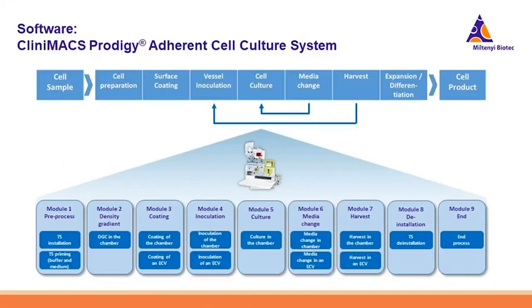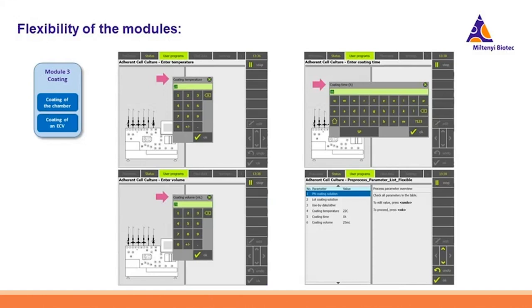Many individual manual handling steps — such as surface coating, vessel inoculation, cell culture, and medium change harvest — can be reflected by the different modules within the adherent cell culture system. Within each module, you can choose either the CliniMACS Prodigy chamber or the external culture vessels (ECV). Within each module, you can also set up all the important cell cultivation parameters. For example, in the coating module you can freely set the coating temperature, coating time, and the volume of your coating reagents, and you also have a summary page to confirm or reset your settings.